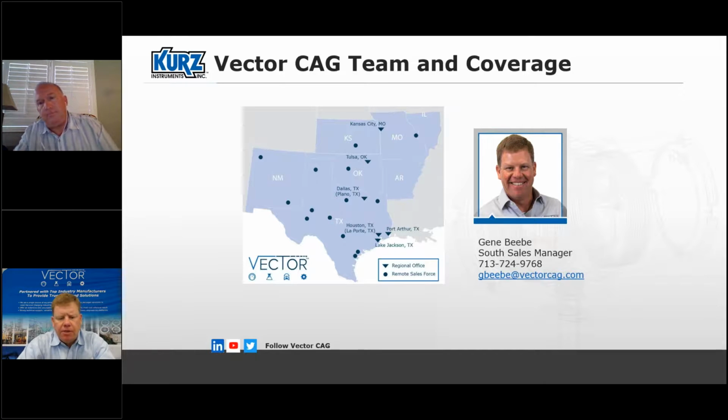Also, how do you make sure that the units are working fine? I mean, how do you calibrate it? How do you test it or verify that the units are working properly? Well, first of all, a Kurz meter has a lot of internal diagnostics already built in. We're looking at about 30 different variables within the sensor continuously, from dielectric strength to the ratio of the two RTD resistances and various other things that are being monitored.